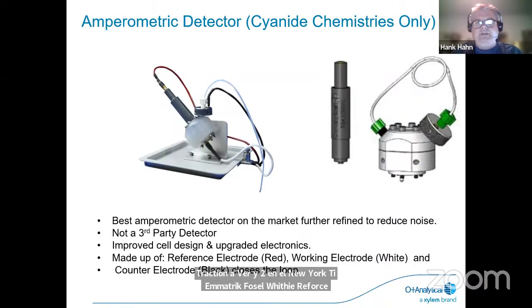With our amperometric cyanide, and again, that's with the cyanide chemistries, it's the best detector for the amperometric style techniques on the market. We redesigned it on the FS3700 to reduce noise. It's not a third-party detector. This is our own. It has an improved flow cell and upgraded electronics. And it's also made up of reference electrodes. Reference electrode is red, working electrode is white, and the counter electrode is black, which then closes the loop.